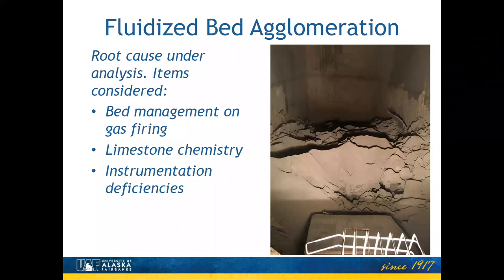What do you mean by limestone chemistry? Oh, one of the emission controls methods that the boiler uses is that there's limestone injected with the coal as it's being combusted, and the limestone attracts the sulfur and other criteria pollutants to it, and it gets collected in the ash, and that's able to be taken out in the baghouse. Right.